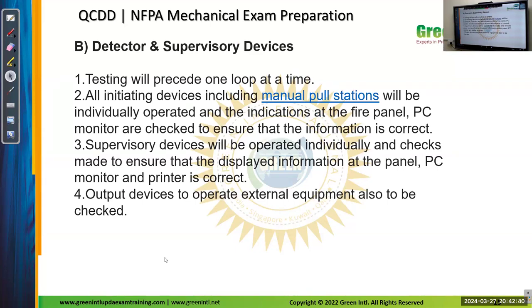Detector and supervisory device testing will proceed 1 loop at a time. All initiating devices, including manual pull stations, will be individually operated and the indications checked at the fire panel and PC monitor to ensure the information is correct. The supervisory devices will operate individually, and checks made to ensure that the displayed information at the panel, PC monitor, and printer is correct. Output devices to operate external equipment are also to be checked. So what we will do is check with the manual pull station and check the supervisory signals at the control panel. We will check that all the signals are coming in and all the functions are working properly.